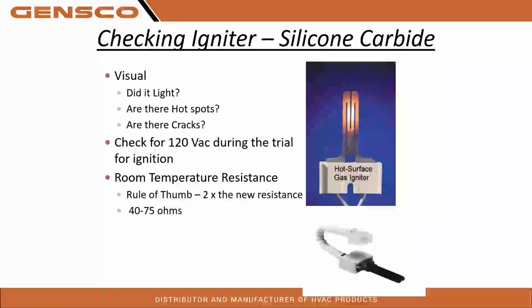Remember the sequence of operation at the very beginning, where you have to send in a call from the thermostat, right? And then it does a self-check, making sure the pressure switches are in the specific position they should be in. So a pre-check, if you will. Then it turns on the inducer, and then does a check after that inducer motor comes on, to make sure the inducer motor did what it was supposed to do and closed whatever respective switches it needed to. And then we'll go into preheat, right? So we'll preheat that igniter. And then after that timing is up, we should get gas valve drop, right? So knowing that sequence of operation, you should be able to time that and go, okay, well, I dropped the gas valve and never saw the igniter.